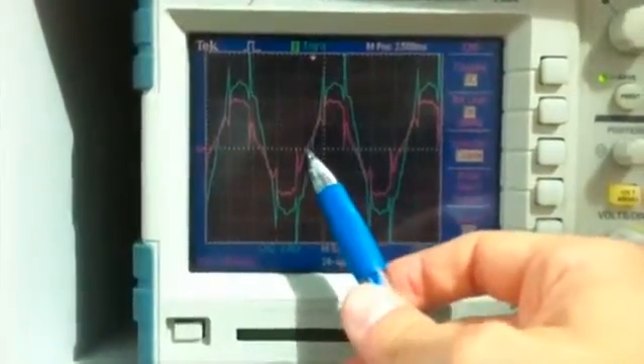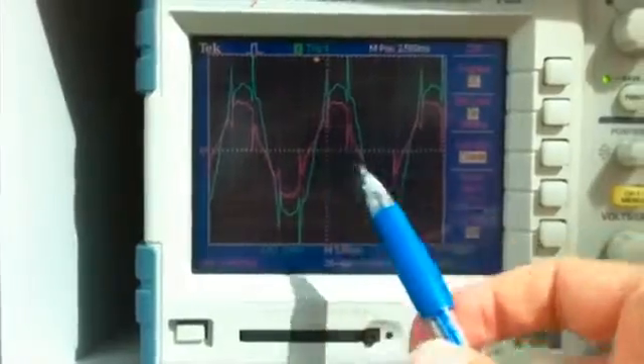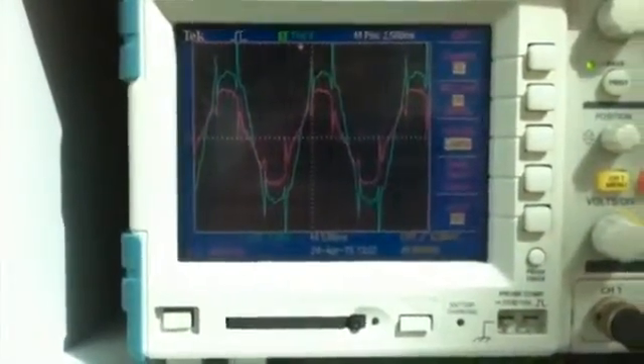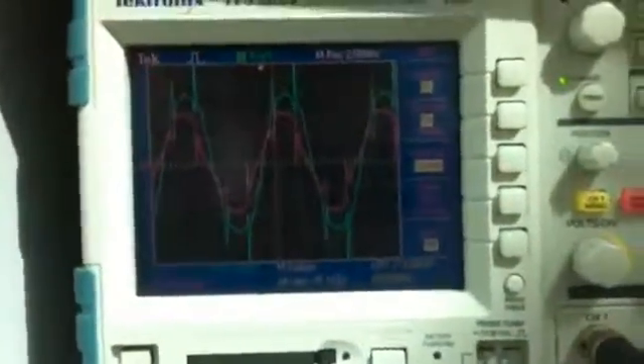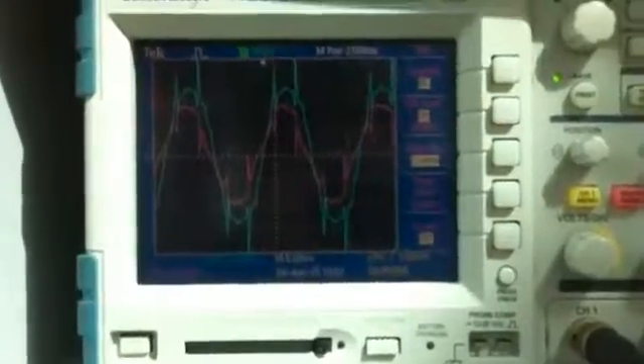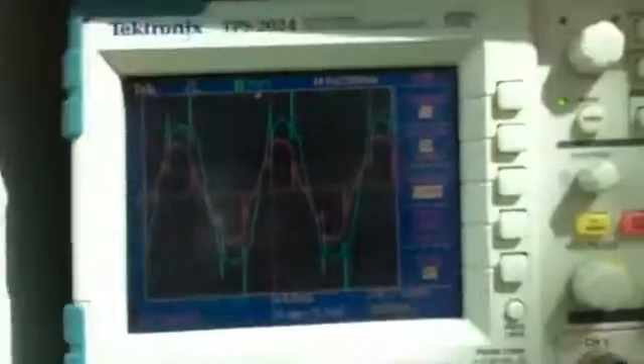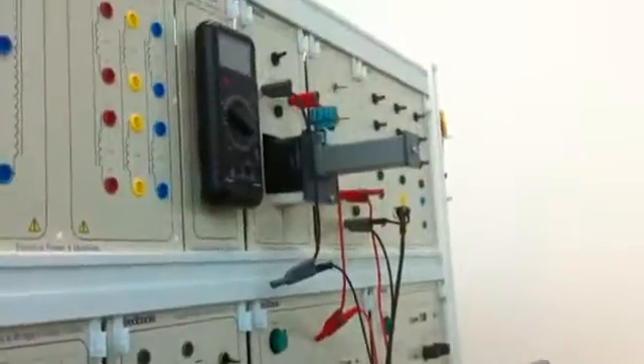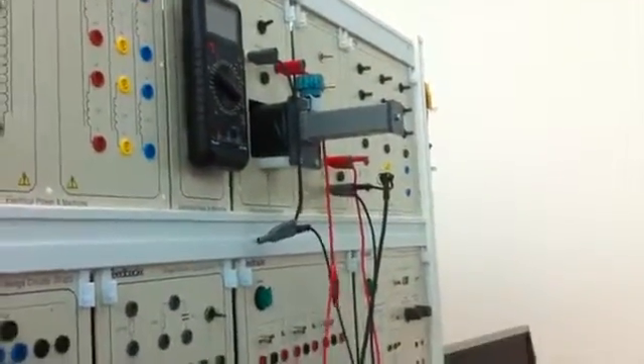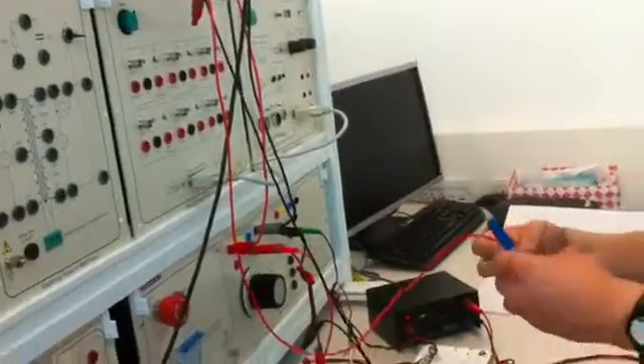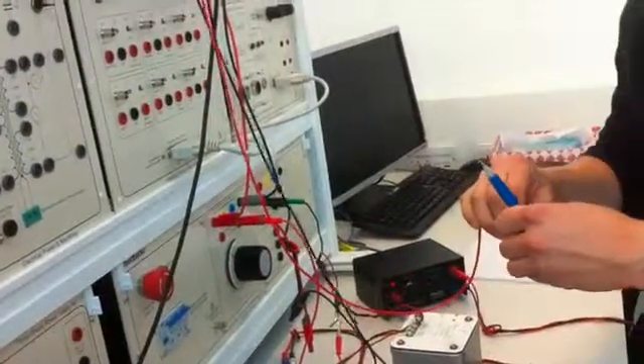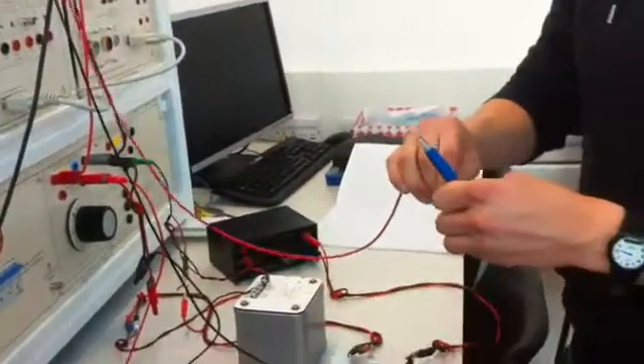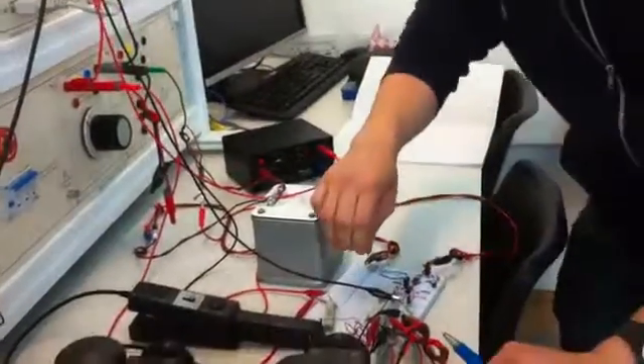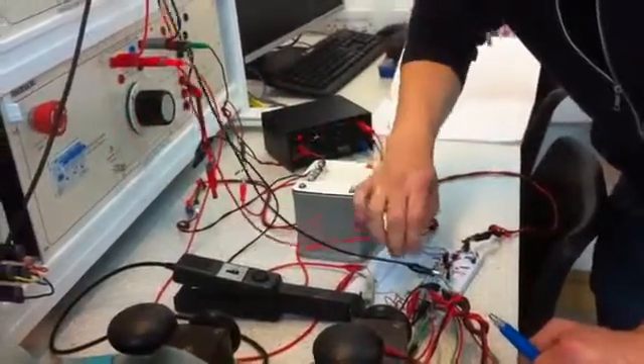Now, one thing that's quite evident is that the current is leading the voltage. That's because at 50 hertz, the filters are primarily capacitive. And to fix that, what I've done is to place an inductor, which I have designed to have the same reactance as the capacitance of the filters at 50 hertz, and applied that over the nonlinear load, which should fix this problem.